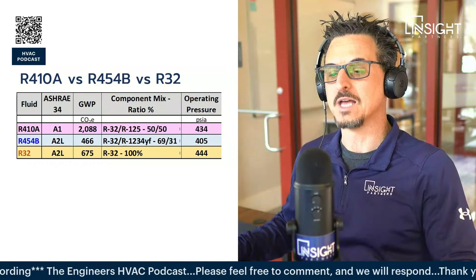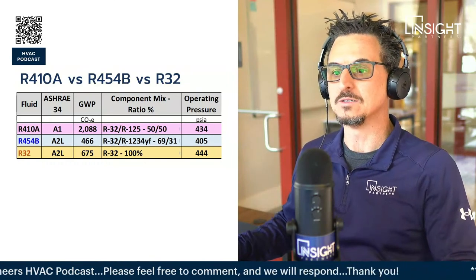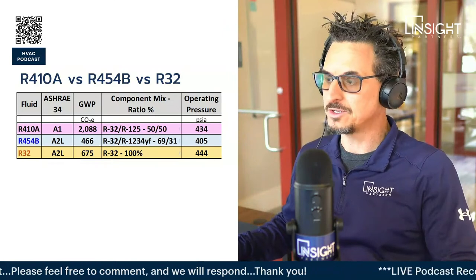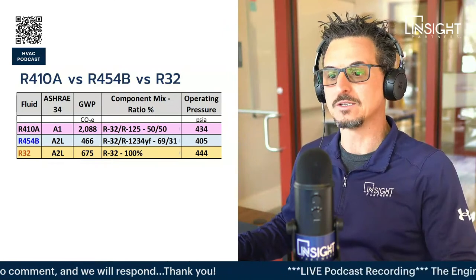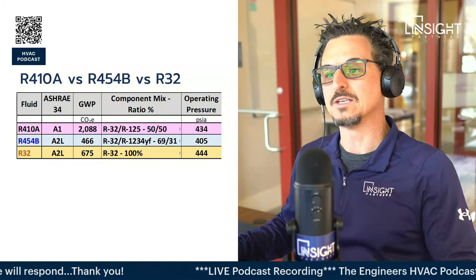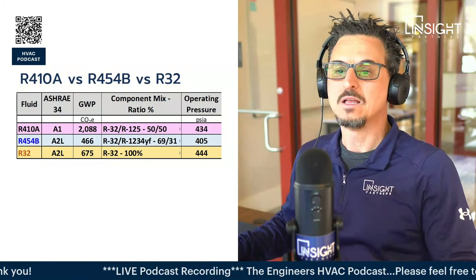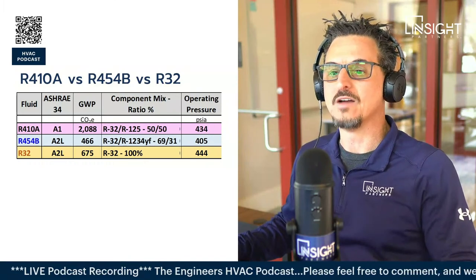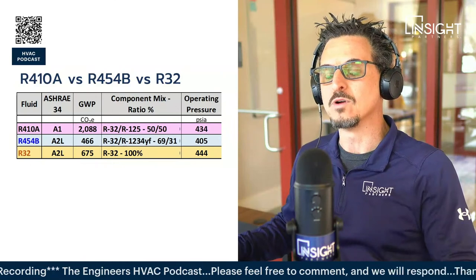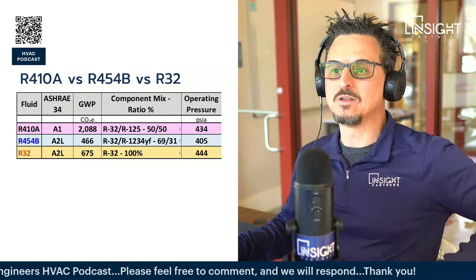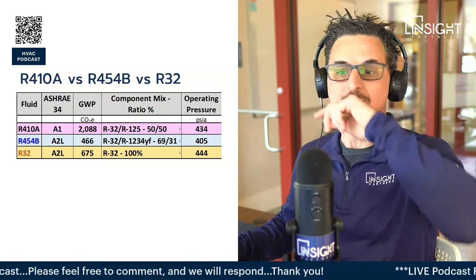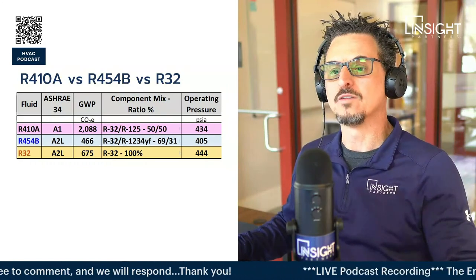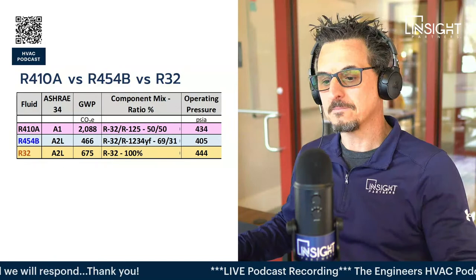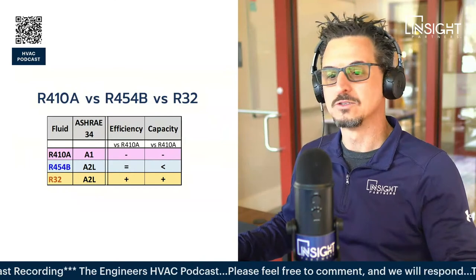Now, R32 is not a blend - it's 100% R32. Some of the operating pressure differences are important to take into consideration as well. 410A is at 434 PSIA, 454B is at 405, and 32 is at 444. So not a huge difference - it's a little bit lower pressure, about 10% lower on the 454B. I believe they all use the same oil too, but I'm trying to confirm that - if somebody knows and can throw it in the chat, that would be super terrific.